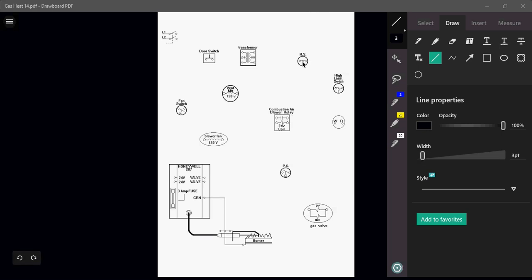We have a rollout switch. We have a high limit switch. We have a fan switch, pressure switch. So again, there we are. We have our control devices: rollout switches, high limit switches, and pressure switches are all safeties in a gas furnace. We have our simplified thermostat here, R and W. Vent motor, again, that's our inducer motor, our blower motor, ignition module, and gas valve.